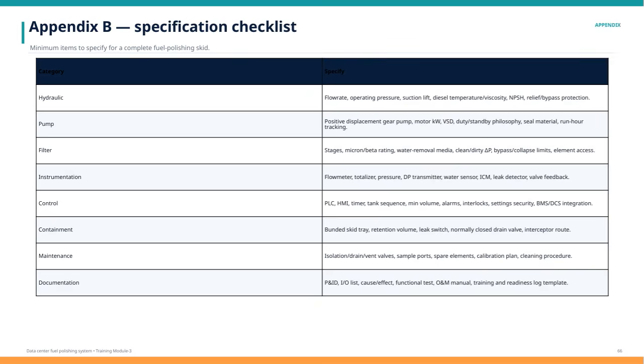Containment must consider features like bund skid trays, retention volume capacity, leak detection switches, normally closed drain valves, and routes for interceptor discharge, all designed to manage leaks and spills safely. For maintenance, specifying isolation, drain and vent valves, sample ports, spare filter elements, calibration plans, and cleaning procedures ensures the system remains serviceable and reliable throughout its life cycle.